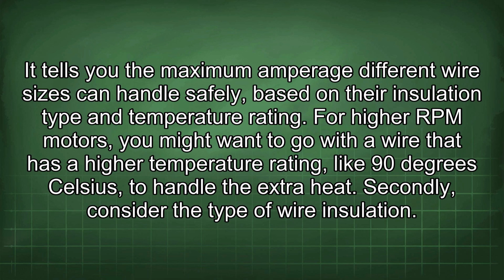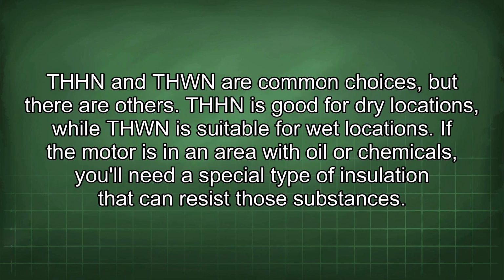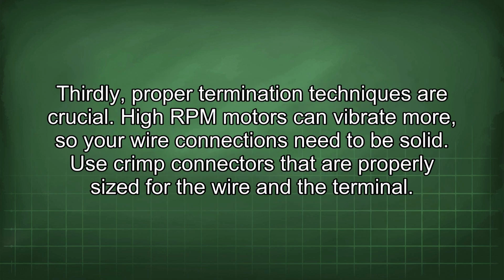Secondly, consider the type of wire insulation. THHN and THWN are common choices, but there are others. THHN is good for dry locations, while THWN is suitable for wet locations. If the motor is in an area with oil or chemicals, you'll need a special type of insulation that can resist those substances. Thirdly, proper termination techniques are crucial.